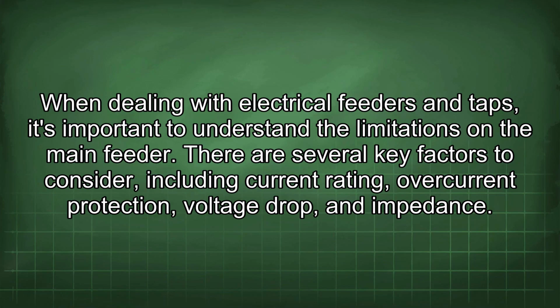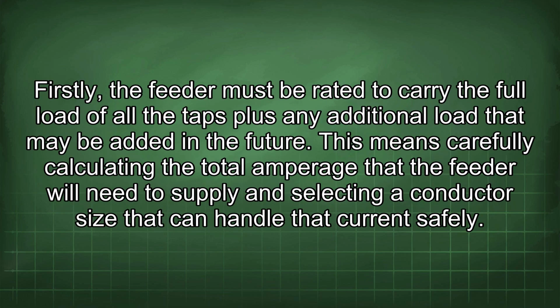When dealing with electrical feeders and taps, it's important to understand the limitations in the main feeder. There are several key factors to consider, including current rating, overcurrent protection, voltage drop, and impedance. Firstly, the feeder must be rated to carry the full load of all the taps plus any additional load that may be added in the future. This means carefully calculating the total amperage that the feeder will need to supply and selecting a conductor size that can handle that current safely.